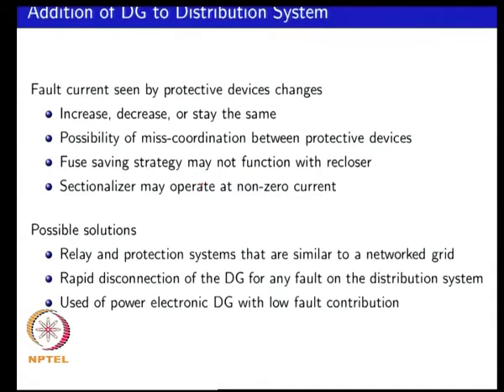One possibility to address the issue of miscoordination between protective devices is to upgrade your protective devices from the simple time overcurrent type of characteristics to something more complex — like what is being used in transmission systems or meshed networks — where you can have multiple sources and try to protect sections of the network using directional relays, distance relays, etc. That would be one possibility, but it drastically increases the cost, which may not be acceptable for a distribution system.